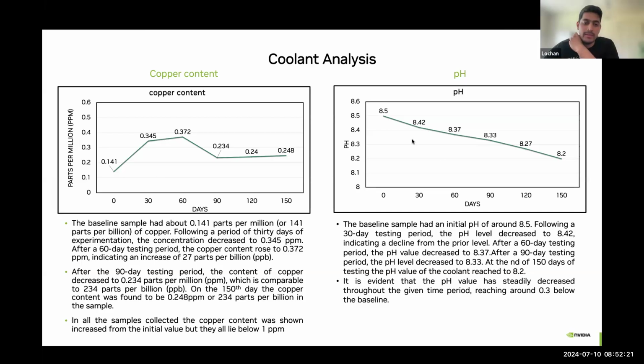Philip, when we have a reservoir in the loop, which is initially at day zero, it is completely filled with glycol. For every 30 days, whenever we are sampling like 750 ml, 1000 ml from the reservoir, that particular volume of liquid is being replaced by air. Even though it is closed, the air present in the reservoir would increase after 60 days when we are collecting an additional 1 liter sample to send for analysis.